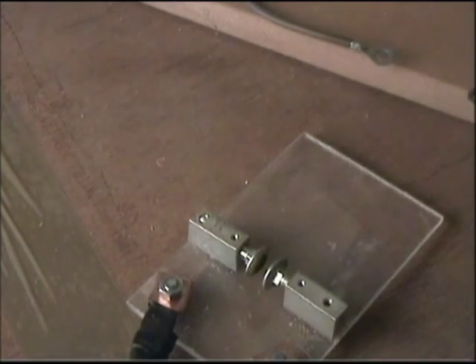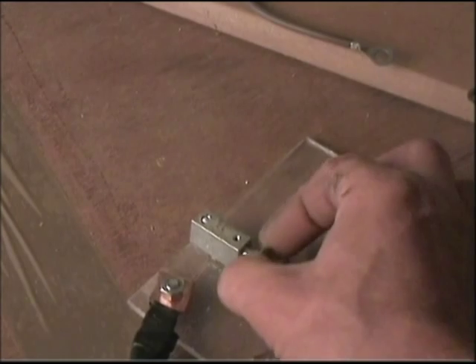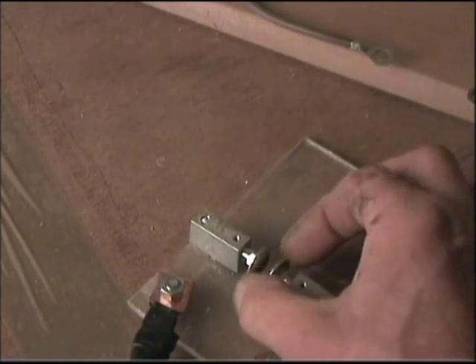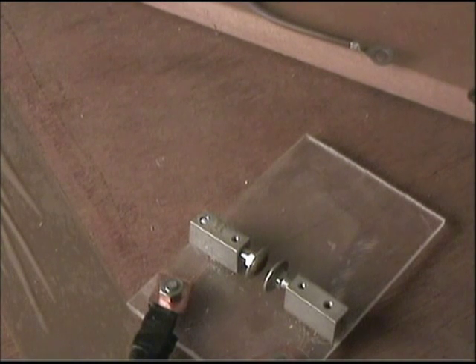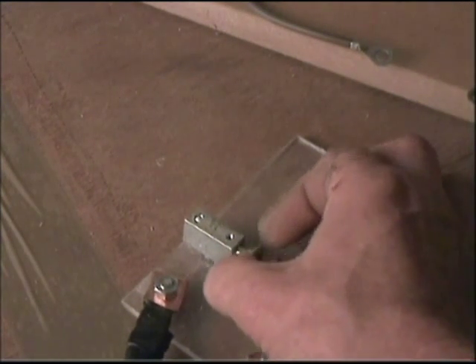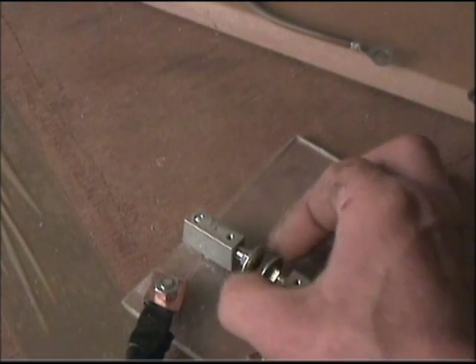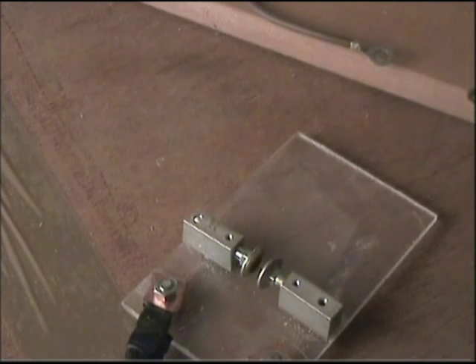Obviously you get to turn off each time you do an adjustment. Now just wound that in probably about half a turn each. Now it is now arcing. And you can go out a little bit. Try it again. No spark on that one. Just keep going in. That one sort of took a bit of time to start. So all you want to do is get a spark that starts reliably every time.